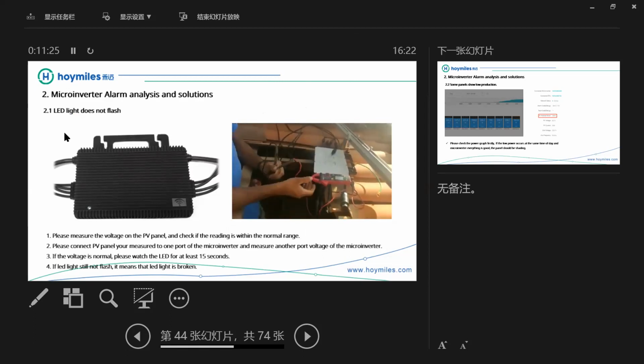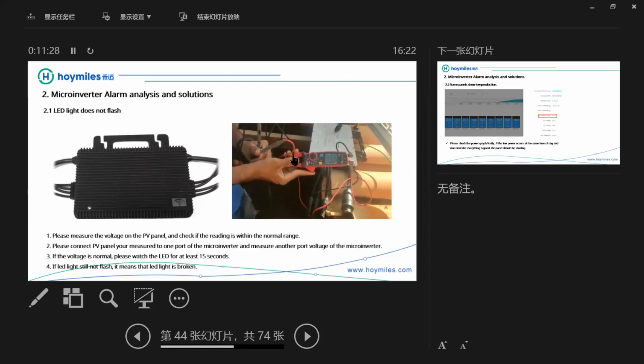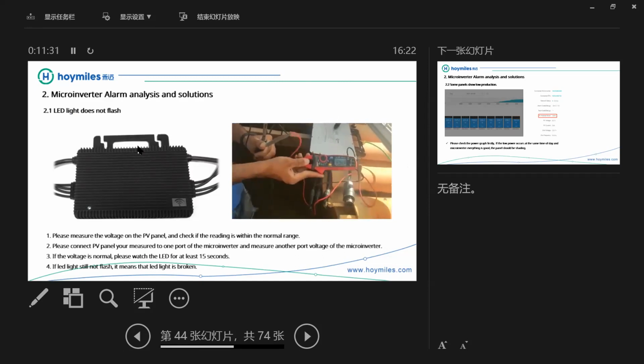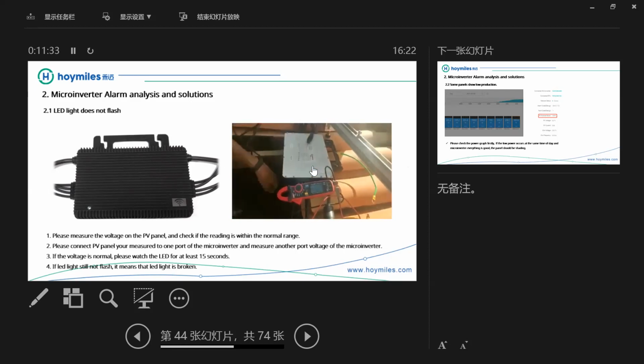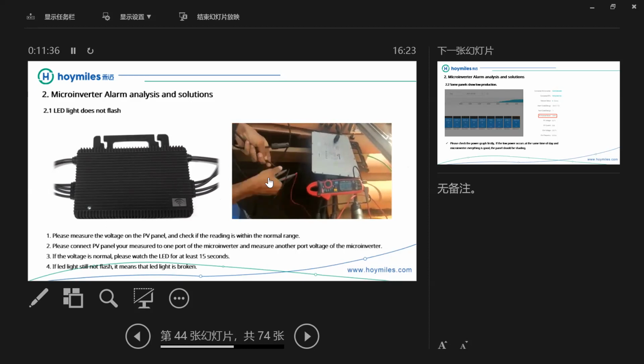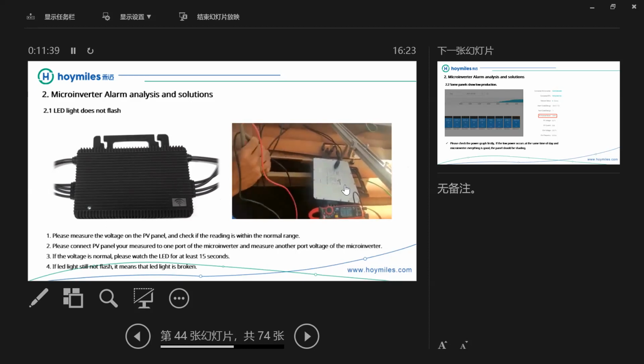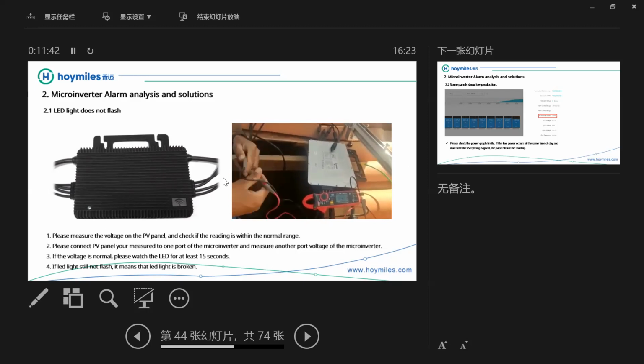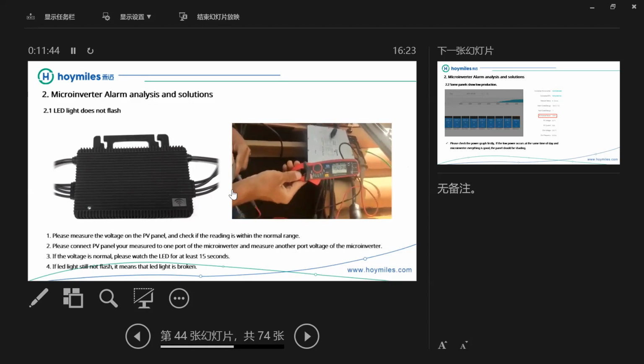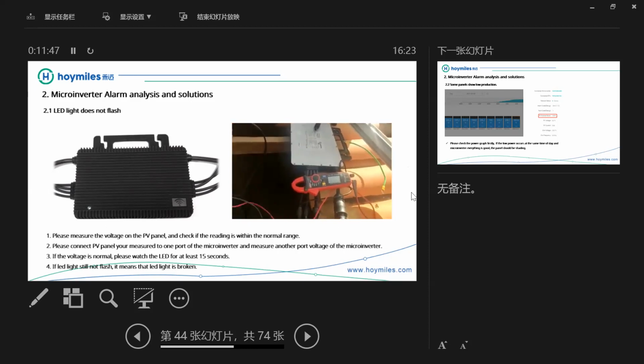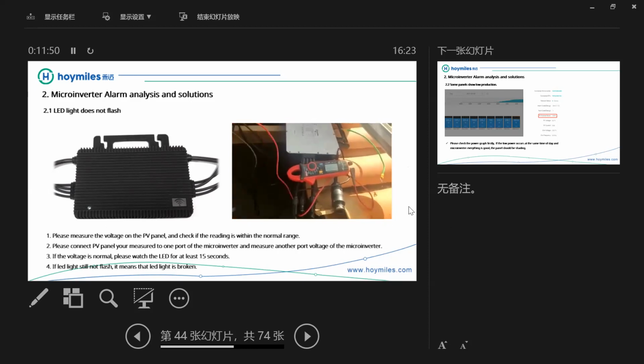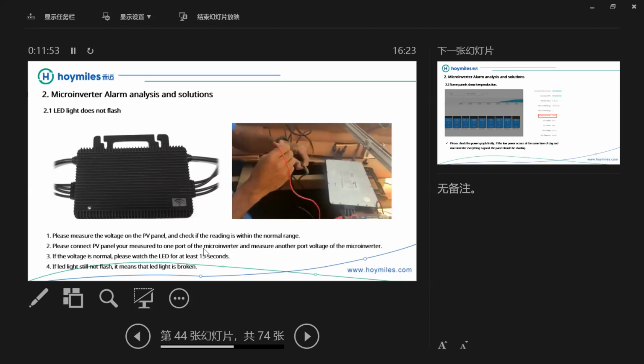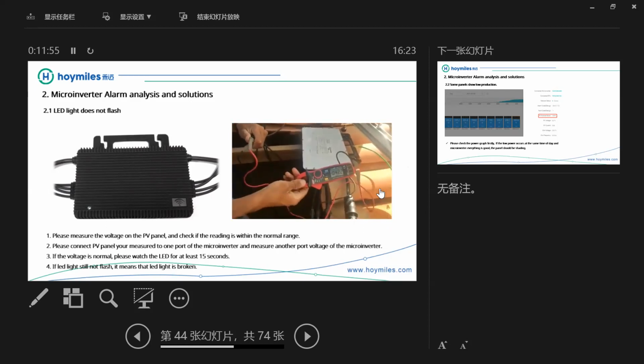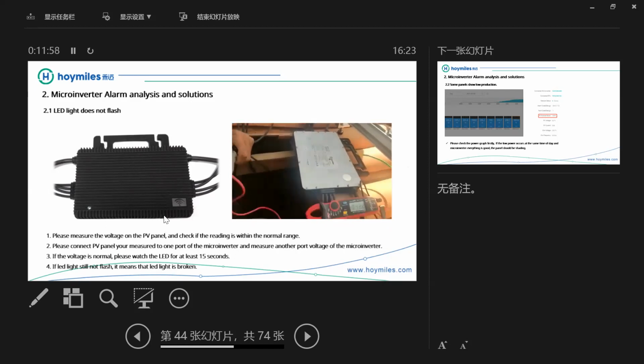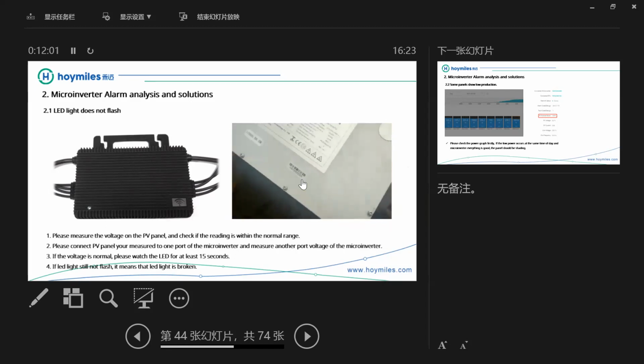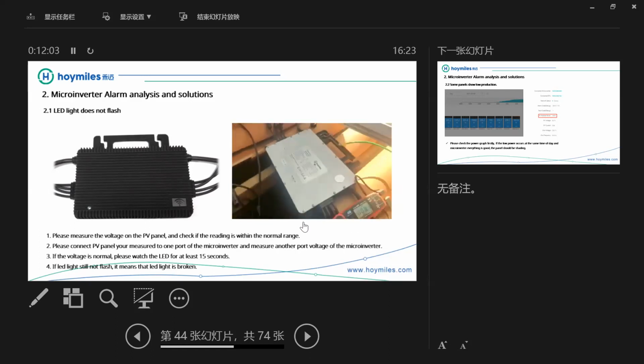Okay, as we can see, this video shows the test protocol about LED light doesn't flash. Now please measure the voltage of the PV panel first and check if the reading is within the normal range. And connect the PV panel you measure to one port of the microinverter and measure another port voltage of the microinverter at the same MPPT side. If the voltage is normal, please watch the LED for at least 15 seconds. But if LED is still not flash, it means the LED light might be broken.